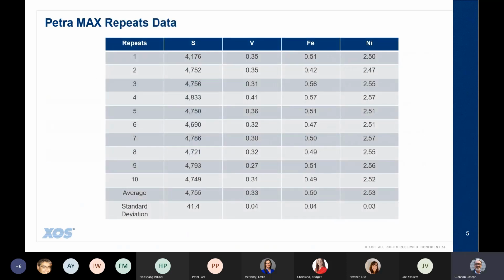Here we're just showing some precision data, essentially some repeats on a sample, testing sulfur, vanadium, iron, and nickel. You'll see with 10 repeats for sulfur, around the 4,700 ppm range, we got a standard deviation of 41. With the vanadium sample with an average result of 0.3, a very tight standard deviation of 0.04. And with an iron sample averaging 0.5 ppm, we have a standard deviation of, again, 0.04. And then a nickel sample averaging 2.5 ppm, standard deviation of 0.03. So some good tight precision there.